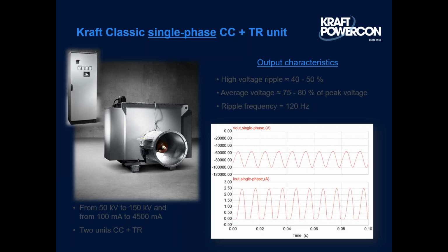But as precipitator efficiencies need to increase, power supplies need to do this as well. With single phase, you have a high voltage ripple of 40 to 50%. If you look at that top waveform, the voltage, if you have a peak voltage of 100 kV, you have a minimum voltage below 60. So that's a lot of efficiency loss.